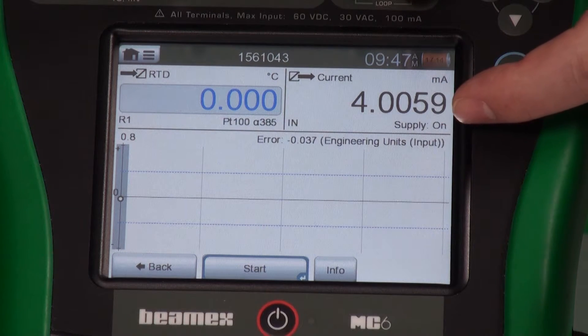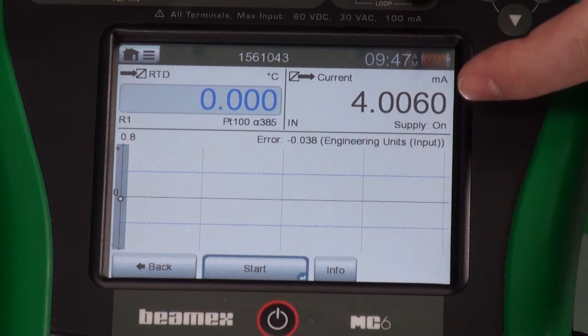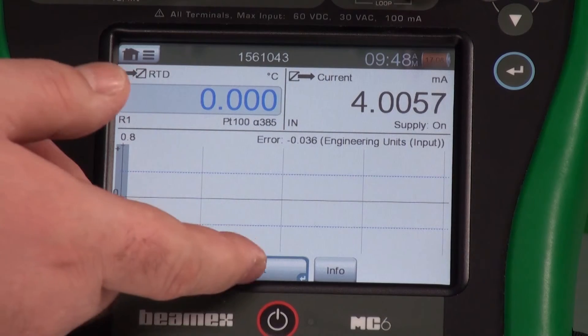You get a live error reading right here on top of the graph. So no matter where you are, you can see in real time if you have an error at this current position or not. And keep in mind, on the bottom right, it will show you what the current test point is that it's driving to. When we start it, it will say 0 degrees in and it's expecting 4 milliamps out. That's more critical on pressure calibrations where you're increasing pressure with a pump or doing manual intervention.